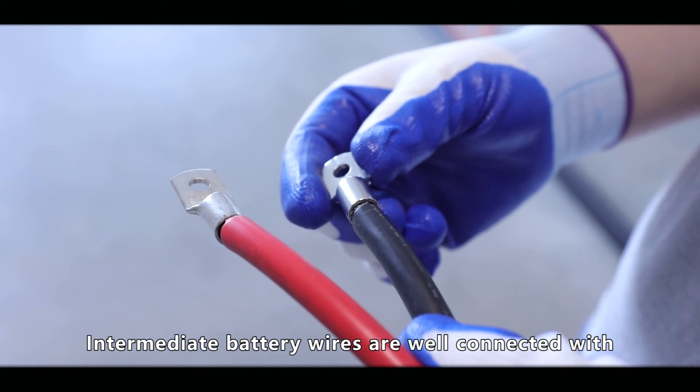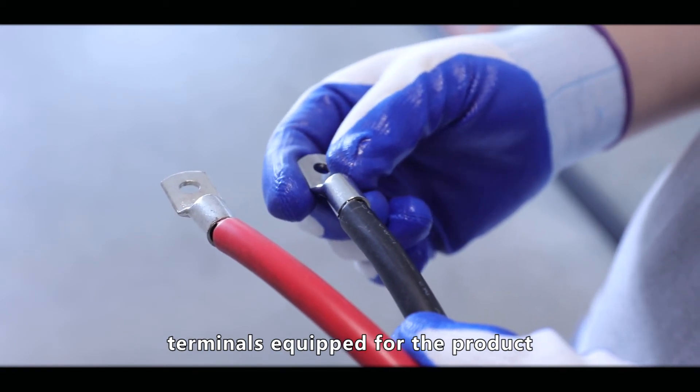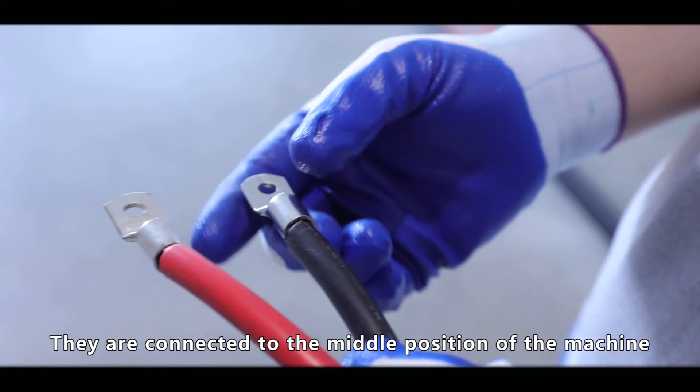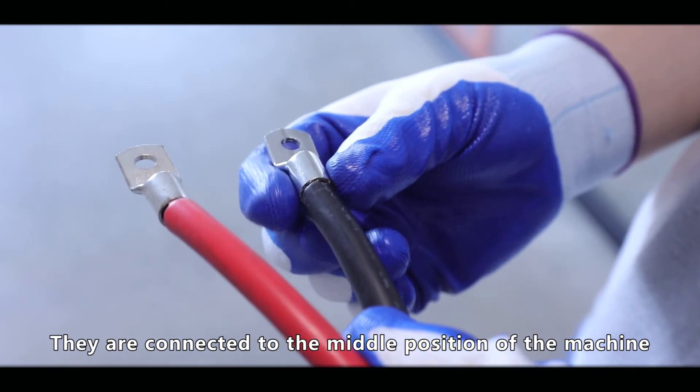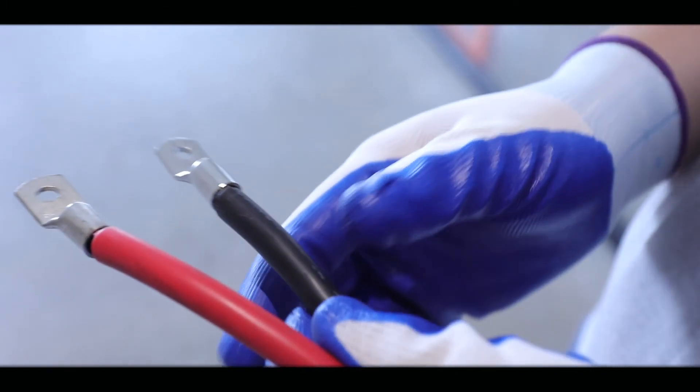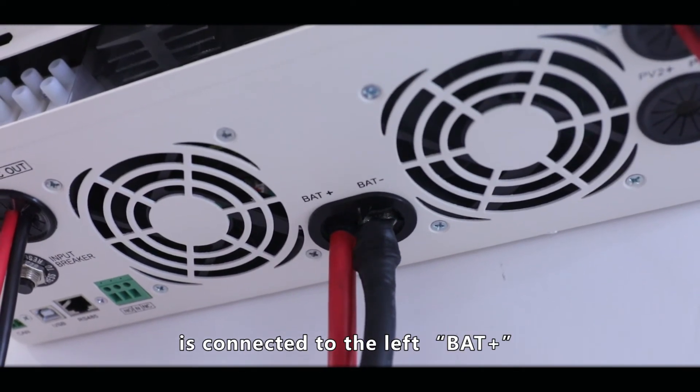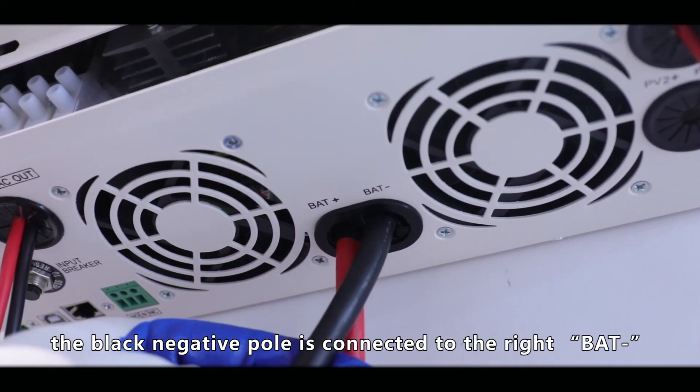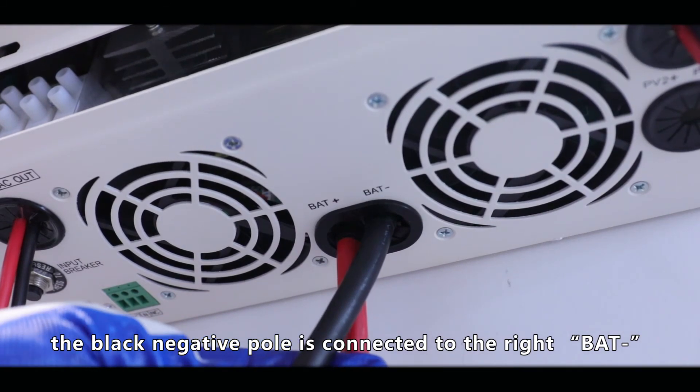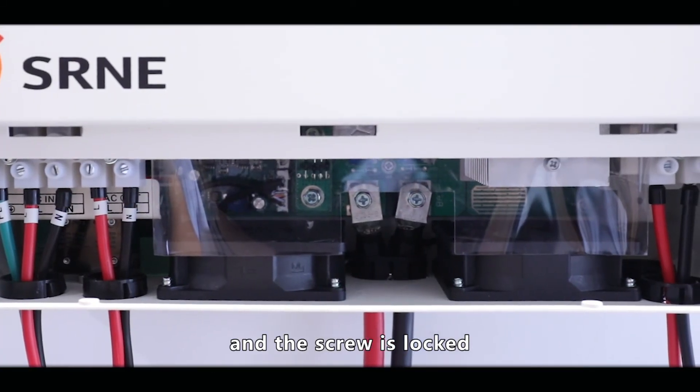Intermediate battery wires are well connected with terminals equipped with the product. They are connected to the middle position of the machine through the middle black guard ring. The positive pole of the red wire is connected to the left, BAT+. The black negative pole is connected to the right, BAT-, and the screw is locked.